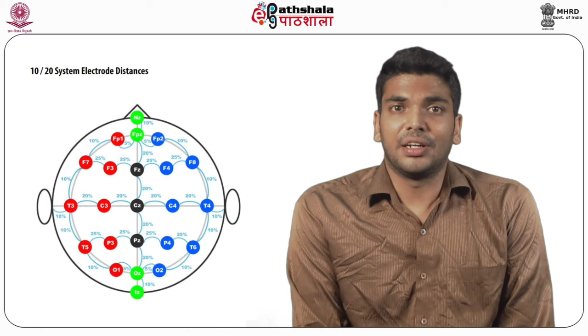Now what we must understand is that EEG as a scalp potential represents the potential difference between 2 scalp electrodes. Now the question is, what 2 electrodes would we consider to be the difference of? Basically any EEG channel represents an electrode pair between which the scalp potential difference is being measured, and a combination of electrode pairs represents something called an EEG montage, which is basically a combination of channels. So that's what we mean by multiple channel EEG. So there's a 19 channel EEG, 32 channel EEG, 64 channel EEG, 128 channel EEG.